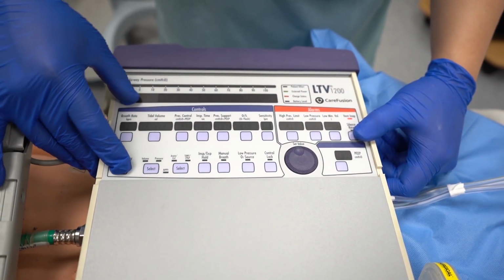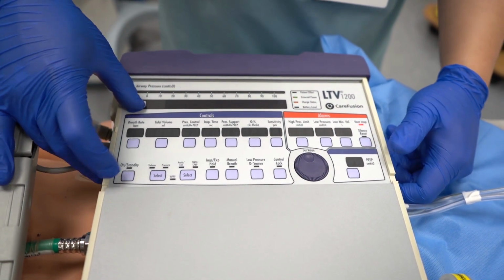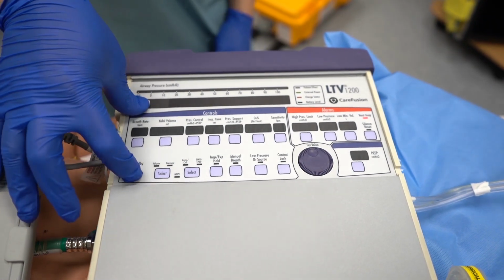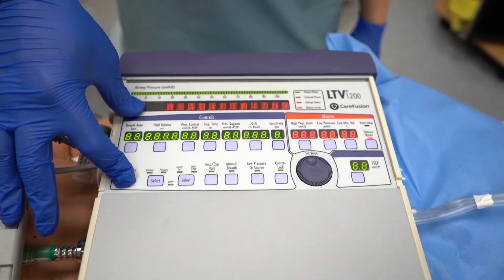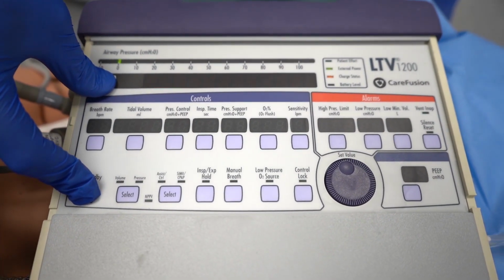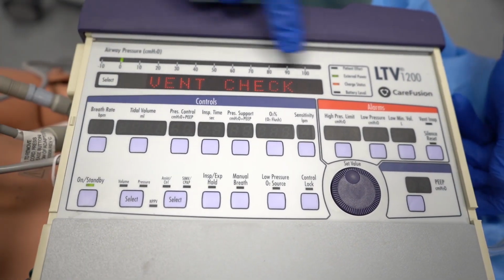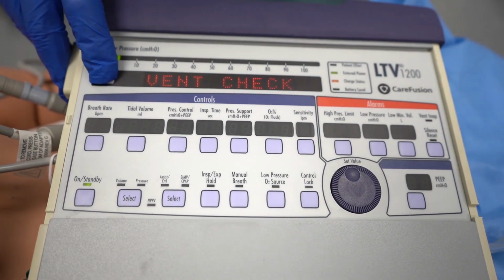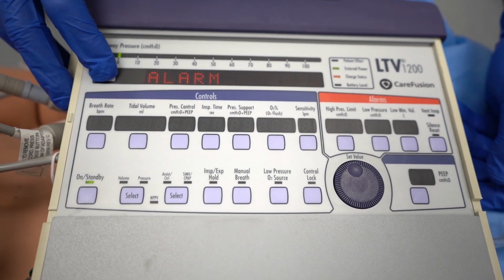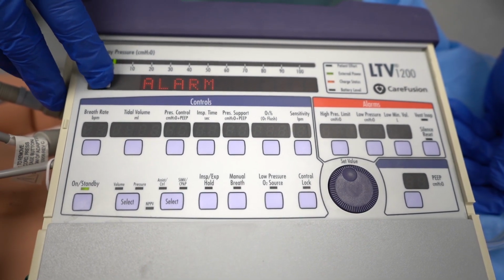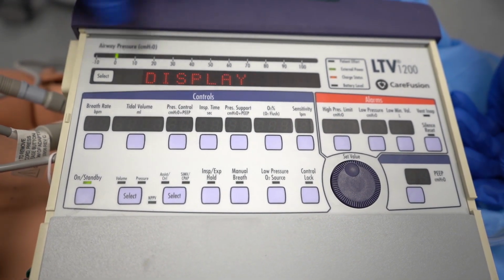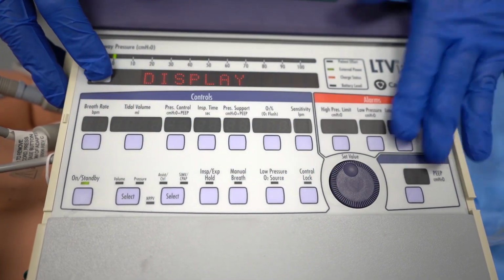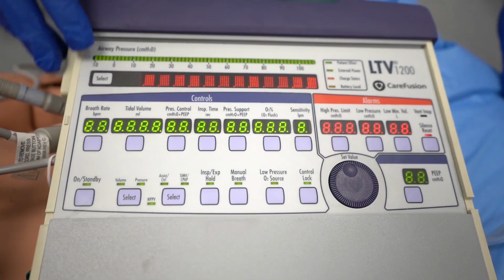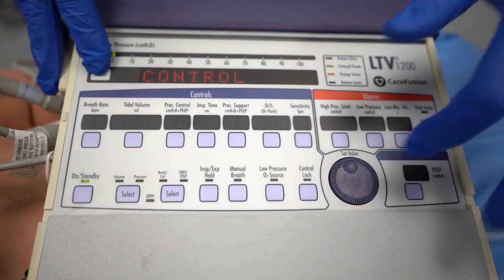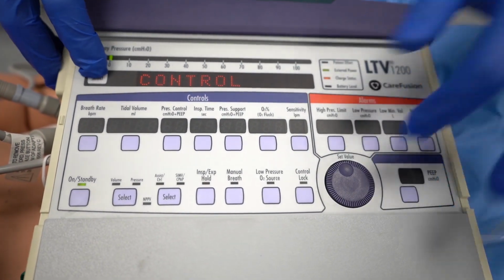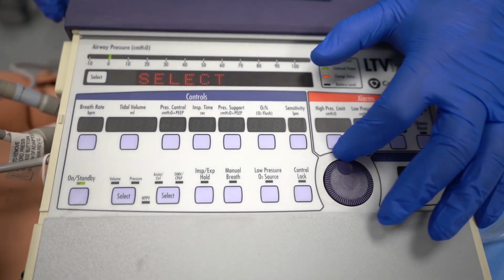Okay, so to turn it on, to start the vent check, you're going to hit select and on, and hold it to turn it on. Okay, silence, and then it'll enter the vent check. So you're going to hit select. The alarms, this is just going to make sure that the alarms are audible. Just keep hitting select to cycle through the different tests. The display is just going to light up the entire screen to make sure all of the lights work. Controls, so the control is going to check on this control knob on the bottom. This is how you're going to change all your settings. So you're going to select.